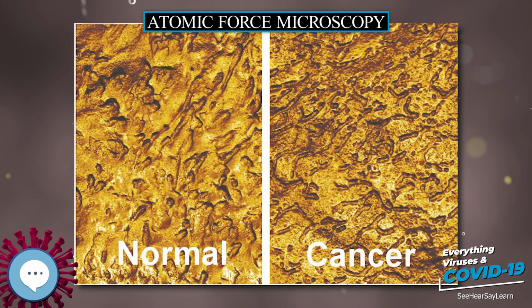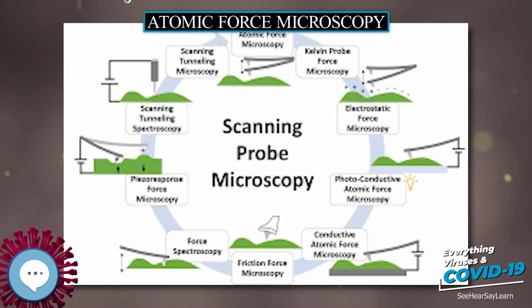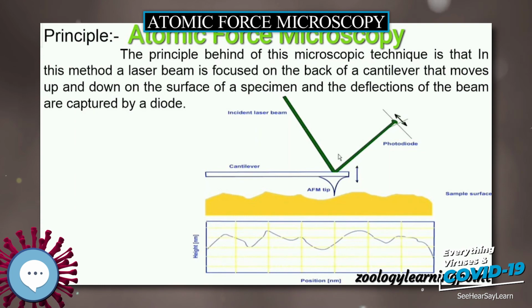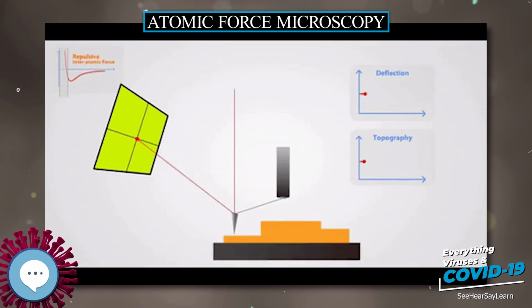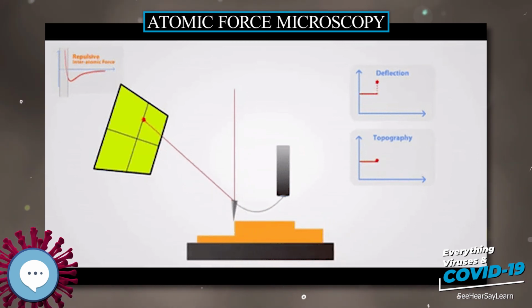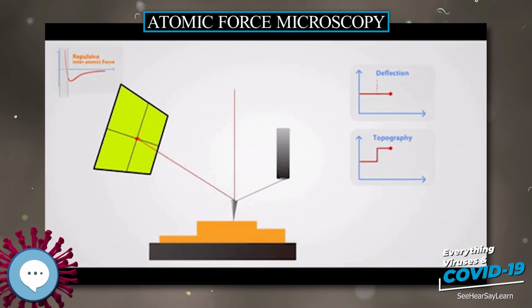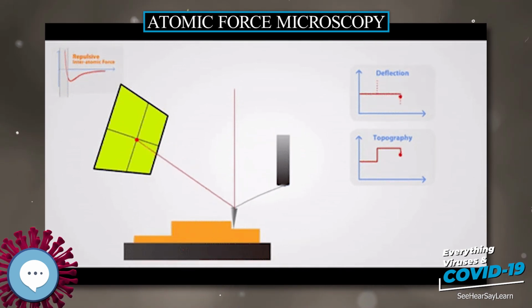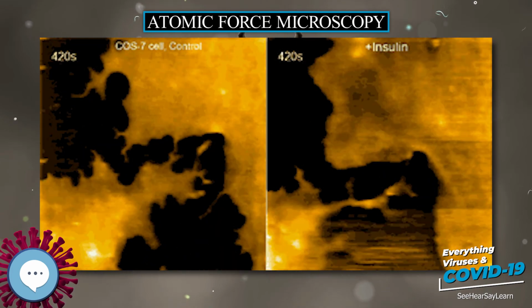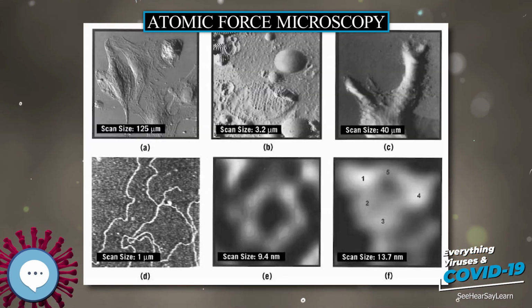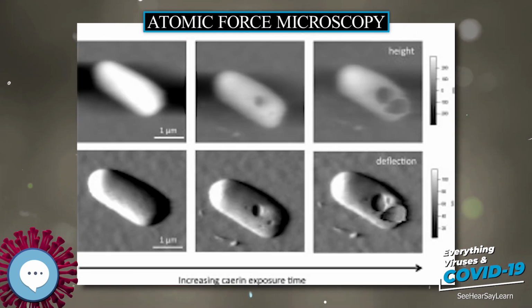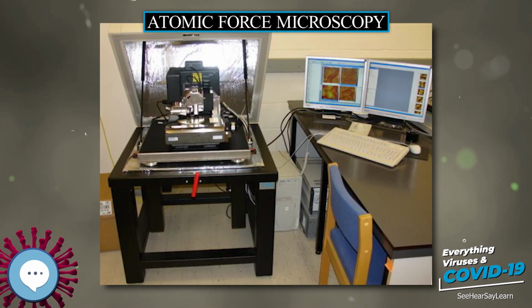To eliminate image distortions induced by thermal drift, several methods have been introduced. AFM images can also be affected by nonlinearity, hysteresis, and creep of the piezoelectric material and crosstalk between the X, Y, Z axes that may require software enhancement and filtering. Such filtering could flatten out real topographical features. However, newer AFMs utilize real-time correction software, for example, feature-oriented scanning, or closed-loop scanners, which practically eliminate these problems.